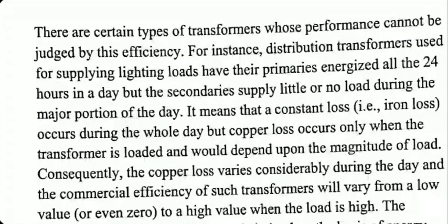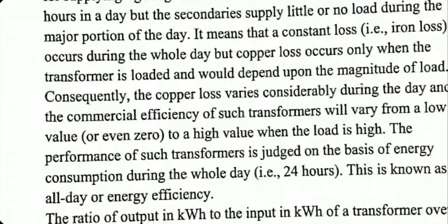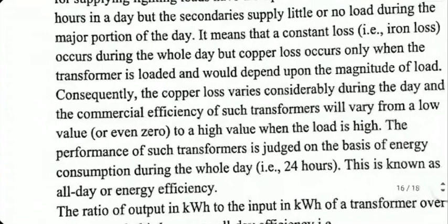Consequently, the copper loss varies considerably during the day, and the commercial efficiency of such transformers will vary from a low value or even zero, because in some cases there will be no power drawn, so it will be zero efficiency. So the commercial efficiency will vary from a very small value to a very high value throughout the day. The performance of such transformers is judged on the basis of energy consumption during the whole day. This is known as all-day or energy efficiency.